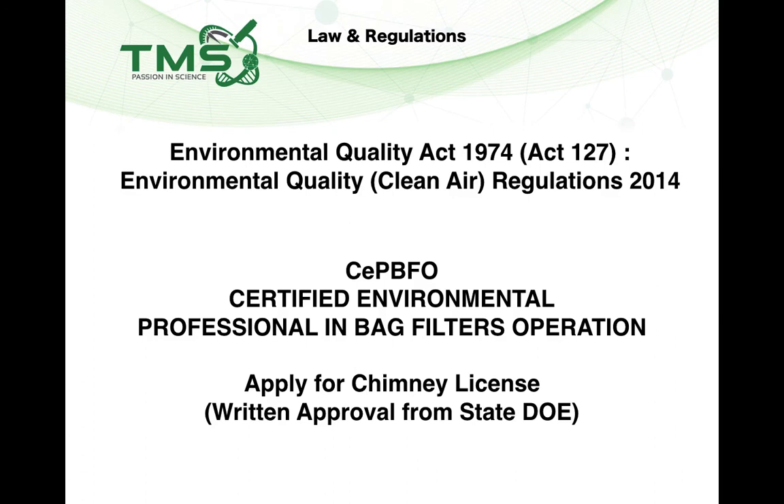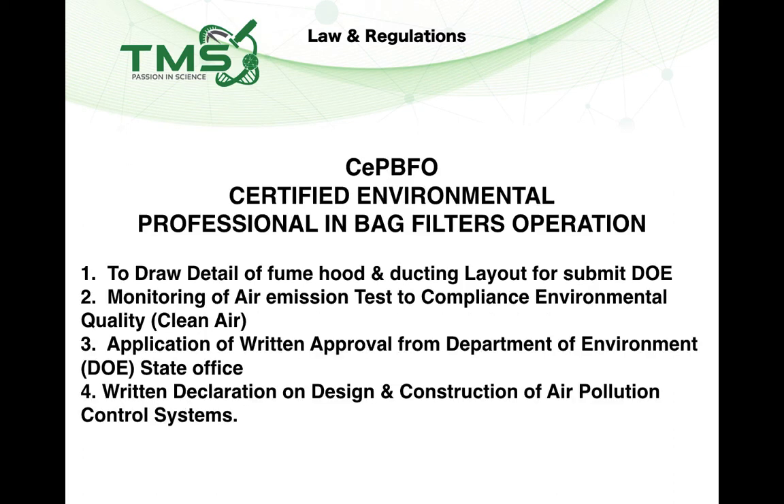Importantly, within 30 days of installation of the stack, you need to obtain written approval from the Director General of DOE. The entire process must be carried out by a competent person — a Certified Environmental Professional in Bag Filters Operation (CePBFO). This competent person will prepare detailed drawings of your fume hood and ducting layout for submission to DOE, perform the air emission test to comply with the Environmental Quality (Clean Air) Regulations, submit applications for written approval from the Director General of DOE, and provide a written declaration of design and construction of the air pollution control system. This process typically takes three to four months to obtain written approval.